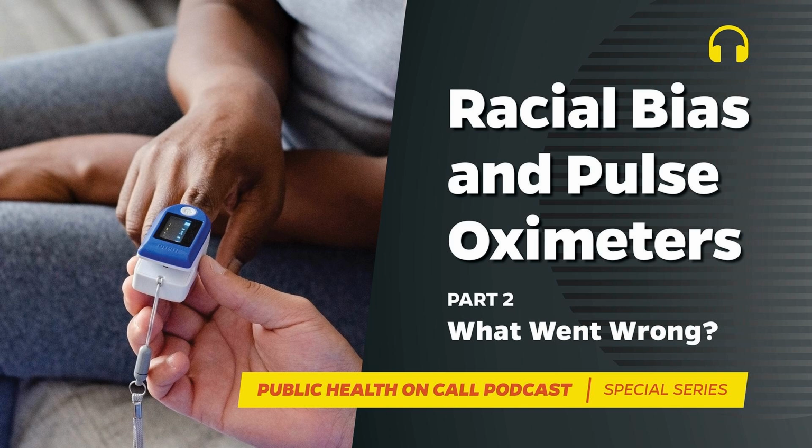When it comes to bringing clinical devices to market and rolled out in hospitals, the FDA stamp of approval is crucial. But until very recently, the agency's standards for pulse oximeters have essentially ignored how skin tone can affect a pulse ox reading. In November 2022, an FDA panel agreed that the available clinical evidence from real-world studies showed that pulse oximeters didn't work as well in people with darker skin pigmentation.